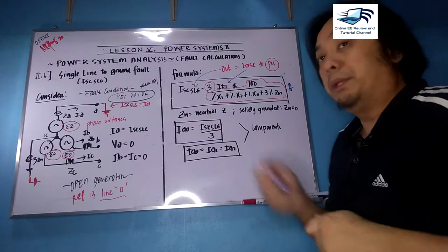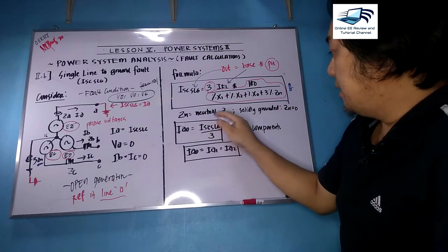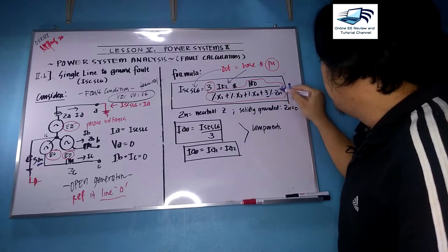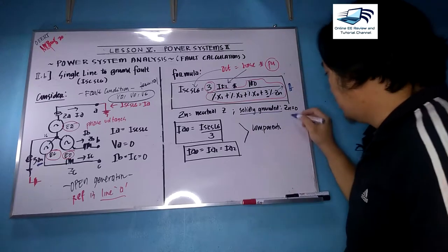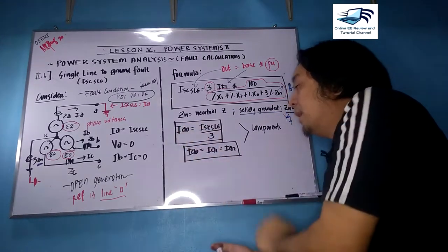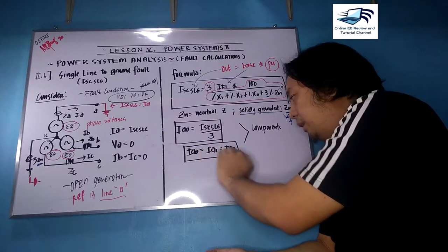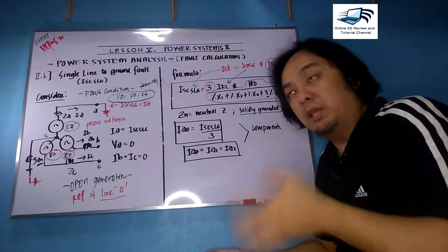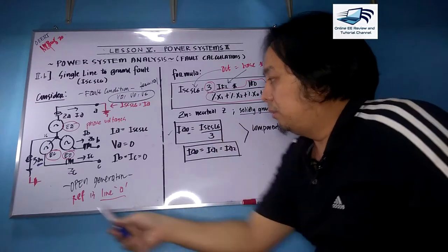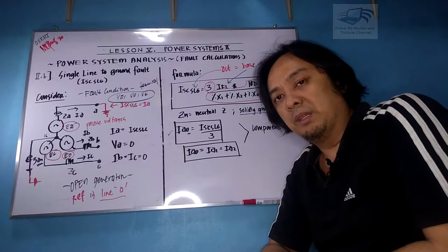We have a new parameter: the neutral reactance or neutral impedance ZN. ZN is always multiplied by 3. It will be eliminated if and only if the system is solidly grounded — meaning ZN is zero. To get the components: Ia0 equals ISC single line-to-ground divided by 3. In a single line-to-ground fault, Ia0, Ia1, and Ia2 are all equal. There is now a zero sequence component because the ground is involved in the calculation.